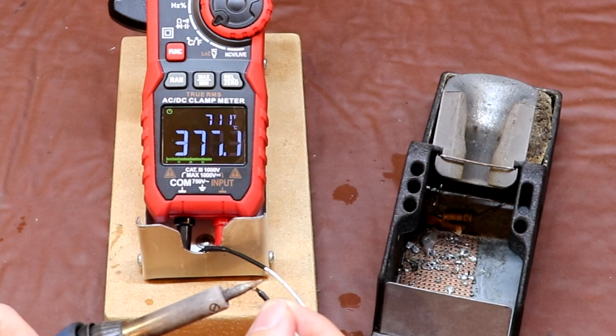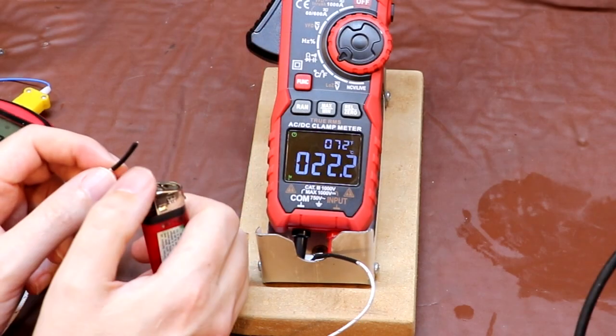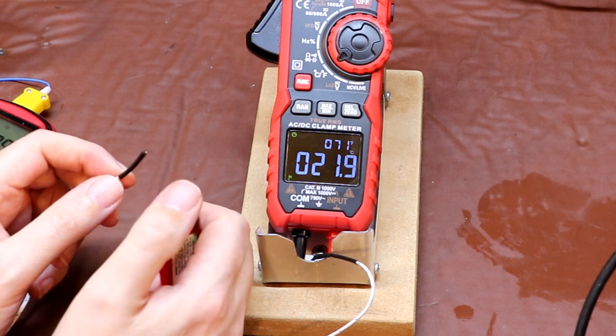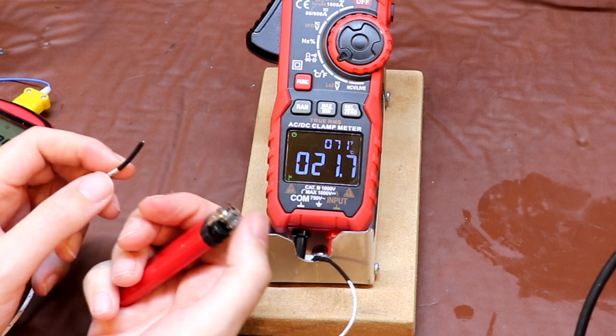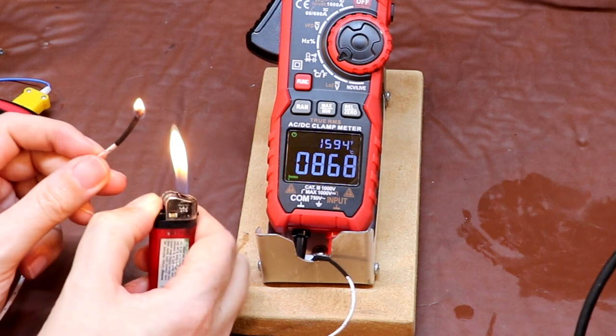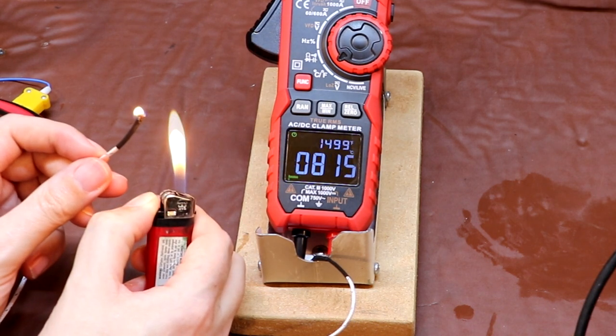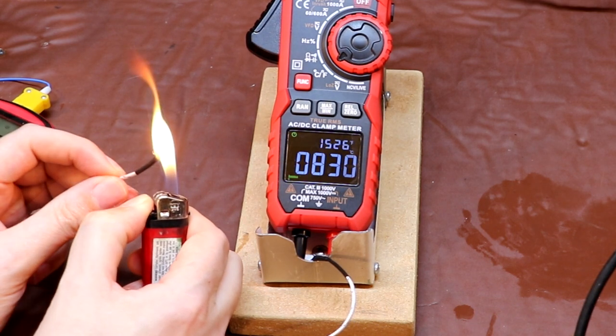Just using my soldering iron now to try to test the upper end of the temperature range. Now I've got my soldering iron set to 360 degrees. Of course it's not going to be very accurate, and the KAIWEETS meter is measuring, well, it's 384 at the moment. The maximum temperature display is specified as 1000 degrees. I'm wondering how hot we can go with a bit lighter here. Well, certainly the thermocouple's now on fire, so I'm guessing it gets quite hot. So that's up to 840 degrees.